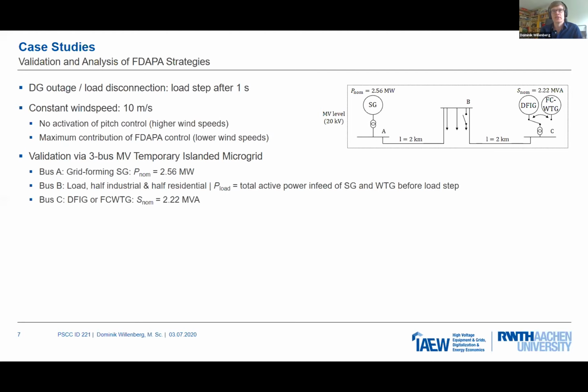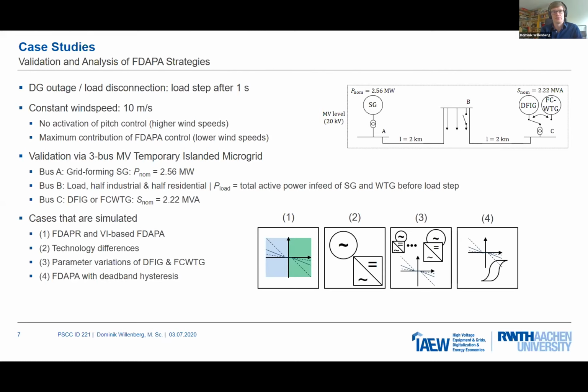island microgrid. At bus A, we have the grid-forming synchronous generator with a nominal active power of about 2.5 megawatts. Bus B is a half industrial and half residential load node, where the load equals the total active power feed of the synchronous generator and wind turbine generators before the load step. And at bus C, the wind turbine generator technology, in that case DFIG or a full converter wind turbine generator, is connected. The cases that are simulated are 4 kinds.